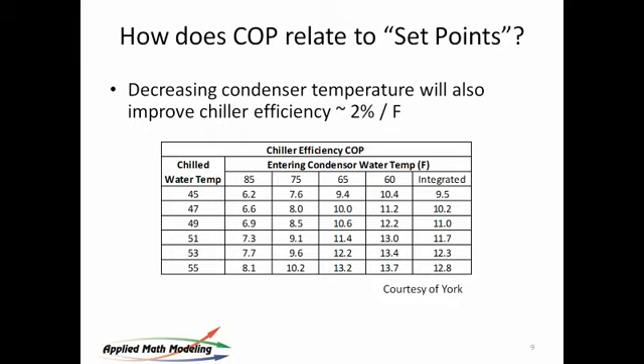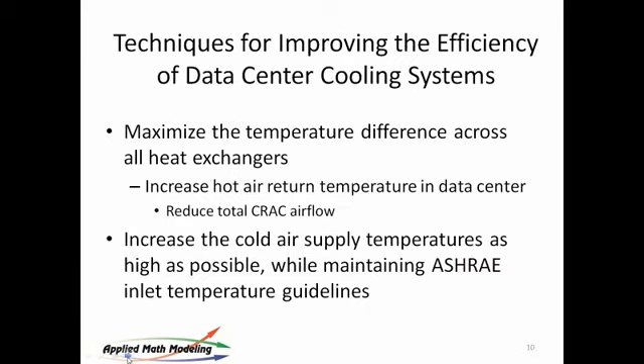Now these are chiller numbers. DX units, direct expansion units that work in the data center, follow the same pattern because they have the same exact cycle. The only difference is in a DX unit, the evaporator is directly exposed to the air, whereas in a chiller, you've got the evaporation loop removed one level through another water loop. There's a water loop between the evaporator and the room itself. Otherwise, they are the same, and there's no reason why a DX unit can't be as efficient as a chilled water system when they're set up correctly. At least that's what most people argue.